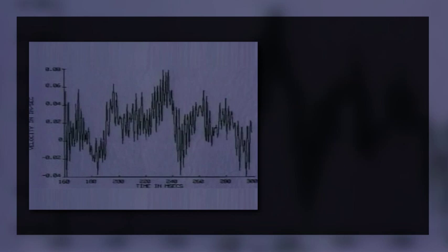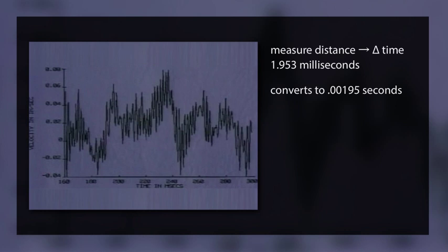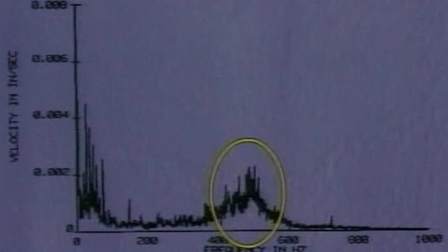If we look at the time domain, we find low-amplitude peaks that are recurring but not entirely uniform. If we measure the distance between two peaks, we find a delta time of 1.953 milliseconds, which converts to 0.00195 seconds, rounded. To convert time to frequency, take the reciprocal: 1 divided by 0.00195 equals 512.82 hertz.